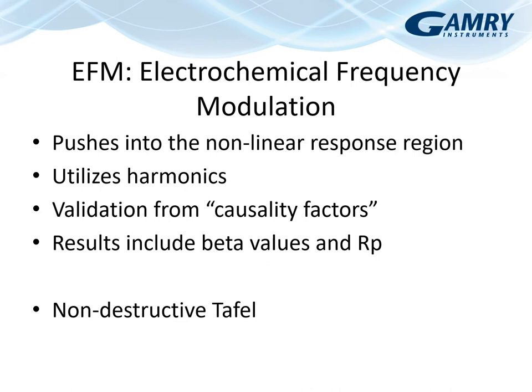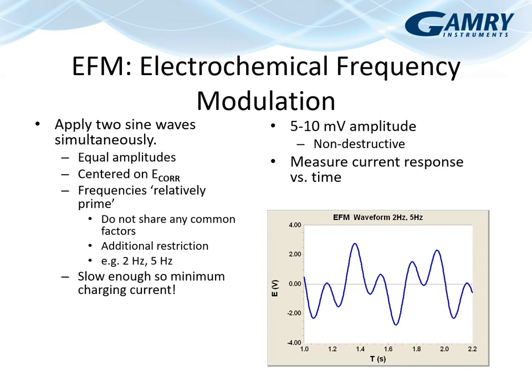Electrochemical frequency modulation provides validation through causality factors, and the data returns both beta values from Butler-Volmer and an R_p polarization resistance value or I_corr. If you're familiar with DC techniques, this is effectively a non-destructive Tafel technique. Two sine waves are applied on top of each other, deliberately pushing into the nonlinear region and generating additional harmonics that allow for collection of useful information. This is not actually EIS, so this is all we'll mention here.